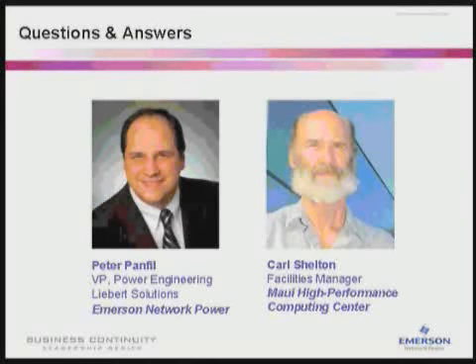I cannot stress enough to keep your documentation, your operating procedures, and your change procedures up to date. These are low-cost efforts you want to do regardless of your data center configuration. The other thing is perform real-world testing. Again, this has a low impact when you make it a part of your operations routine. And do that availability quick test. This will help you focus on if there's additional hardware changes that are warranted. And I will always stress that your primary focus would be on eliminating single points of failure. Carl, can you add anything to that from your perspective in Maui? Yeah, that single point of failure issue is something to give some strong consideration to when you're planning anything. Again, I'm one of those infrastructure first kind of guys.